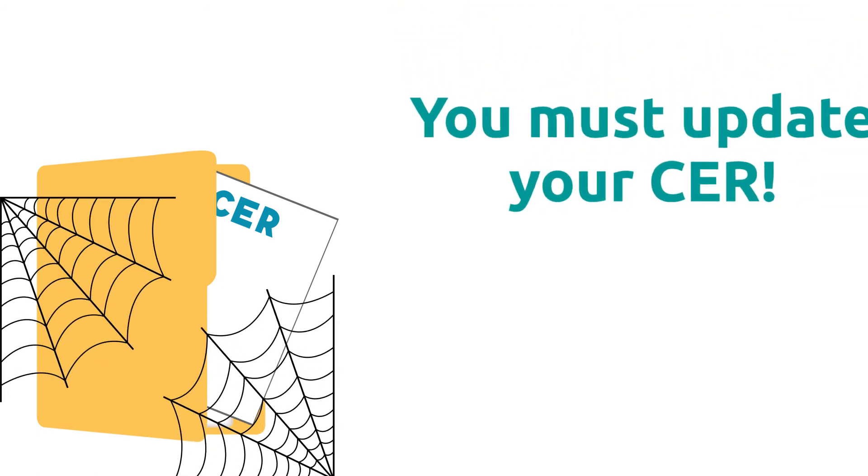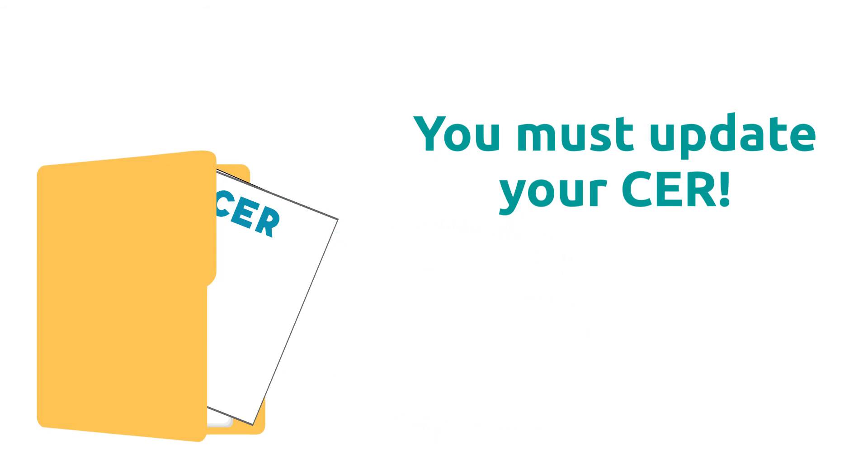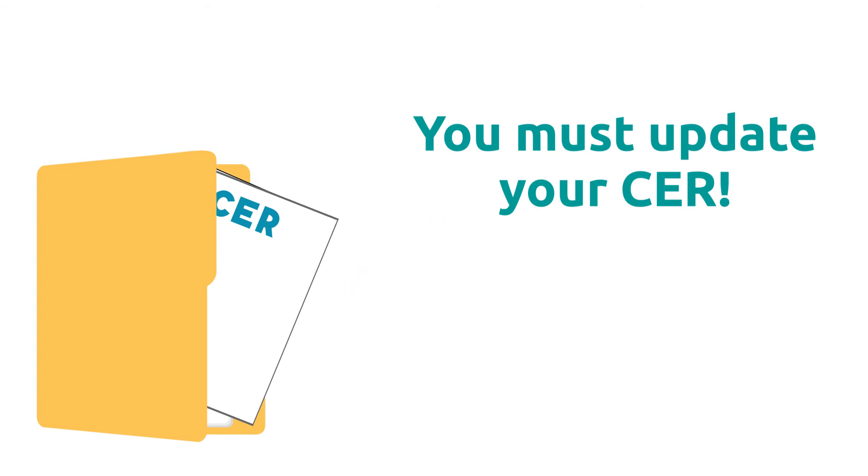Many manufacturers make a big mistake in assuming that the CER is done once, then placed on a shelf. The fact is it needs to be continually updated as part of your post-market surveillance or vigilance activities. Any notable changes that impact the initial data collected should be recorded, and the CER must be appended accordingly.